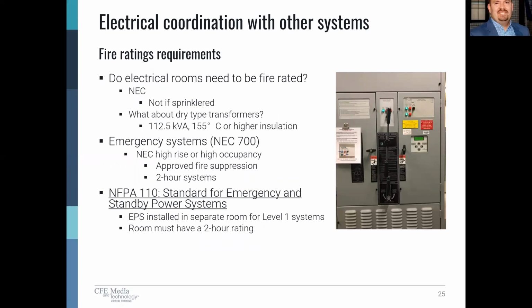So Brian touched on this just a little bit in his discussion about fire protection. Do all electrical rooms need to be fire rated? Well, no. If the room is sprinklered, we don't necessarily need to rate the room. But there is a specific case in the NEC where we often do run into requirements for fire rating of a particular electrical room. In the case of a 112.5 kVA transformer in an electrical room, if that transformer does not include 155 degrees C or higher insulation interior to the transformer, then that room would ordinarily be required to be rated.